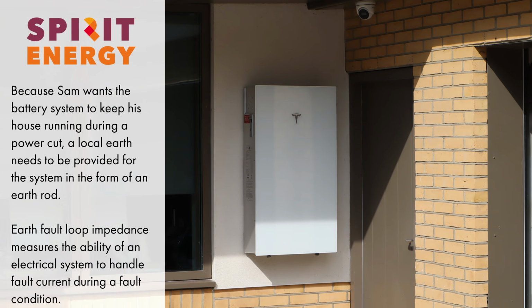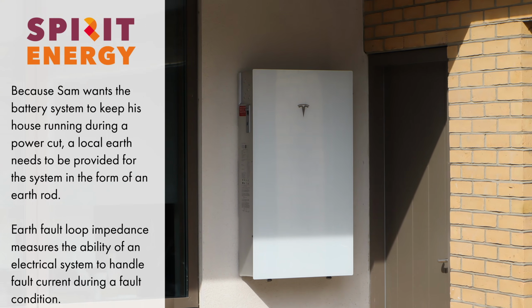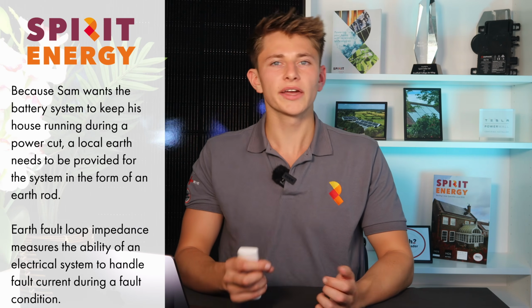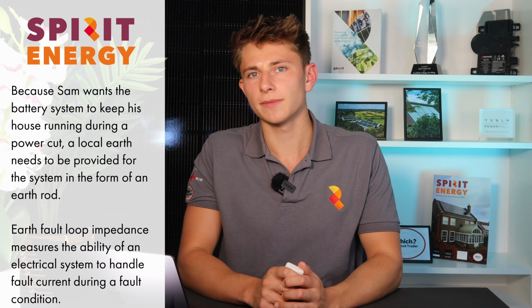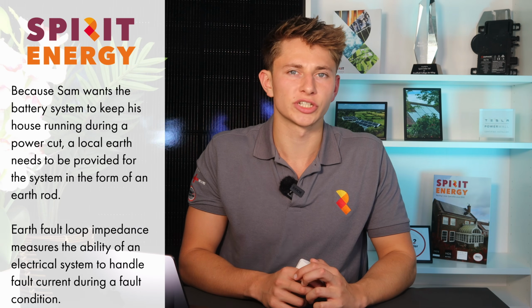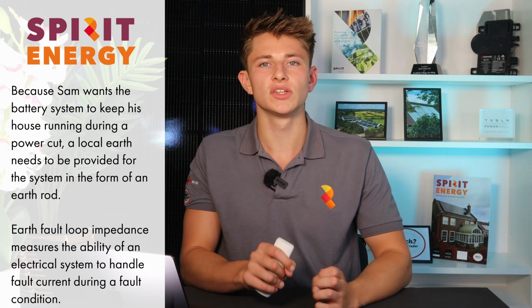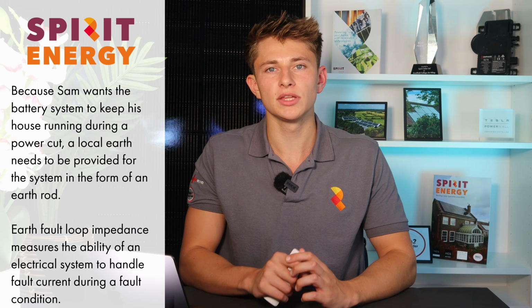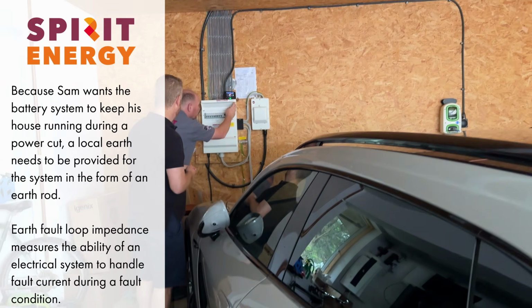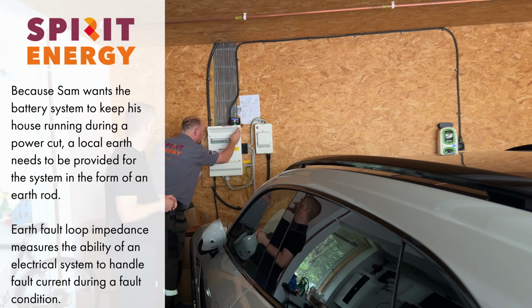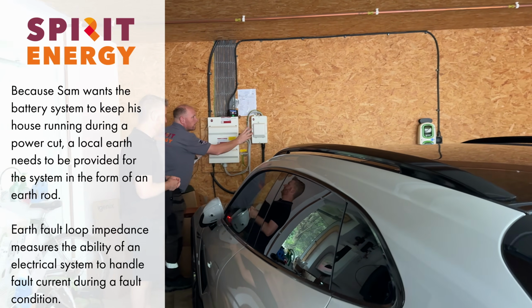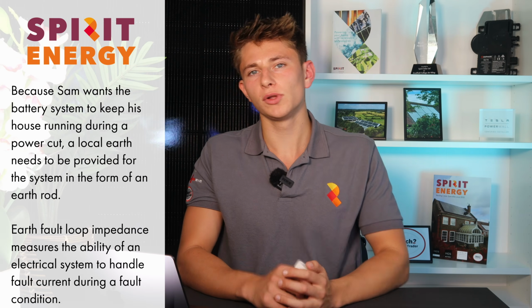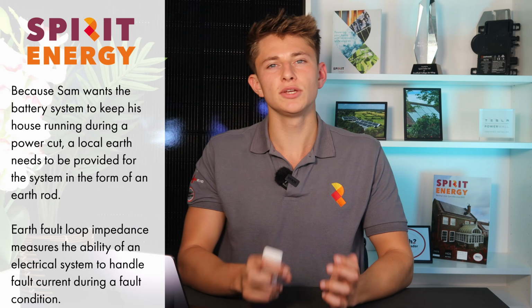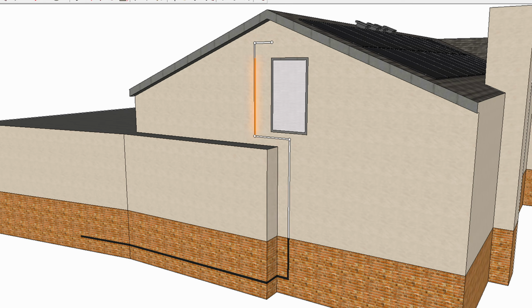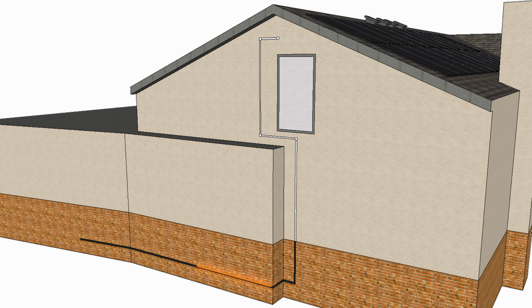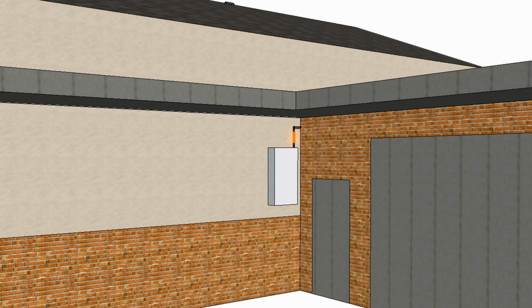As Sam is getting a Powerwall 3 that is capable of full house power cut protection, it needs to be fitted with an earth rod. Occasionally there's an existing earth rod on site, and Justin or one of our other electricians will check the earth fault loop impedance to make sure it can be used and that we don't need to fit another one. In Sam's case, the only thing connected to the earth rod is an old style EV charging point, and the results of the earth fault loop impedance test showed that we could use the earth rod for the Powerwall 3.